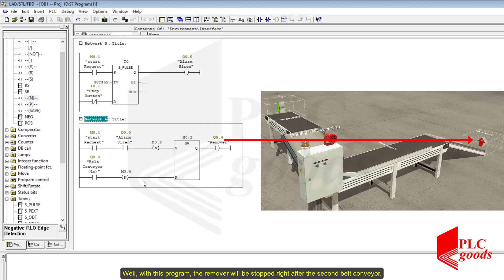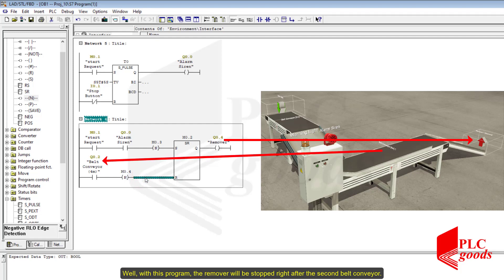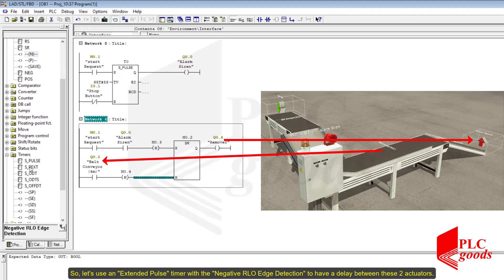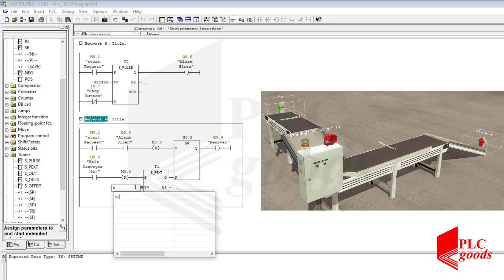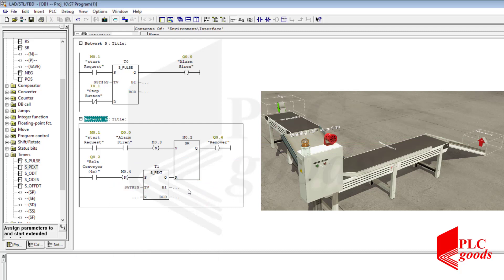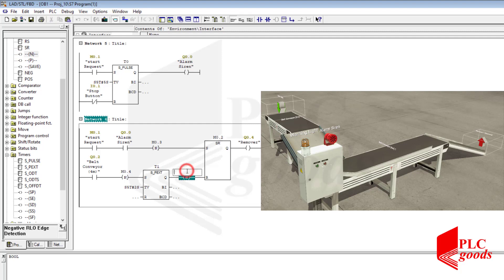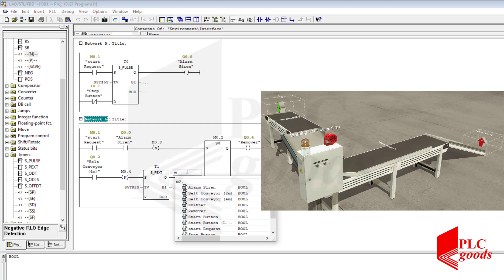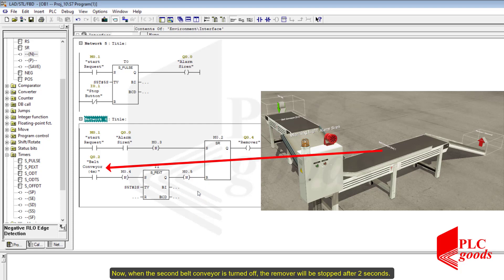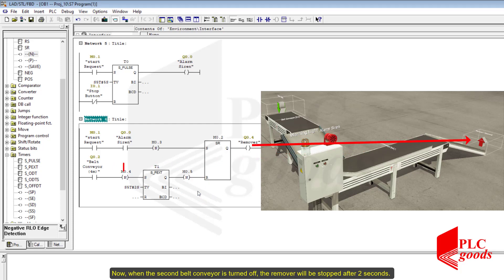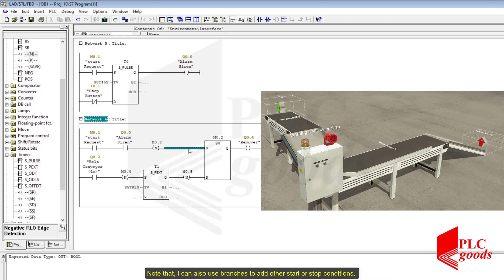With this program the remover will be stopped right after the second belt conveyor reacts. So let's use an extended pulse timer with negative edge detection to have a delay between these two actuators. Now when the second belt conveyor is turned off, the remover will be stopped after two seconds. Note that I can also use branches to add other start or stop conditions.